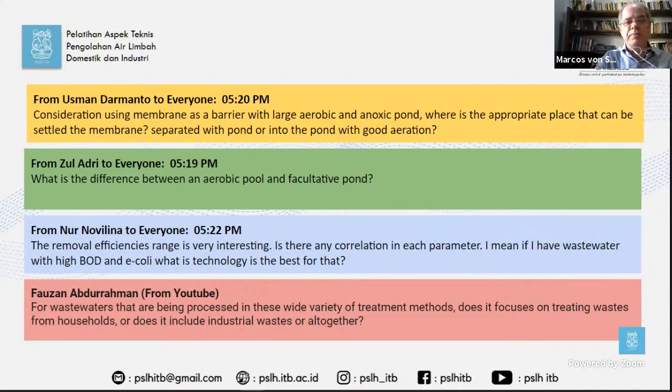Some cities in the urban area also receive industrial wastewater. If the industries are nearby, they can discharge their effluent into the public network collection system, and the combined sanitary or domestic wastewater and the industrial wastewater is treated together. But this will depend on the location of the industry. And the industry needs to remove certain things before. If the industrial effluent has toxic compounds, heavy metals, or things that can cause problems in the network, problems with the safety of the operators, they have to be removed.